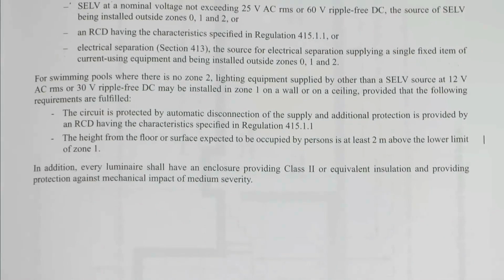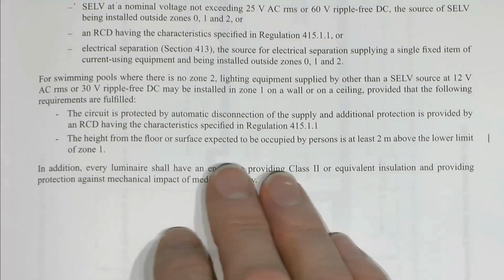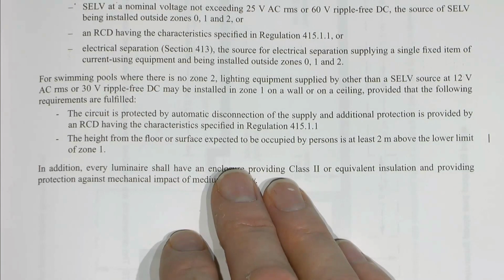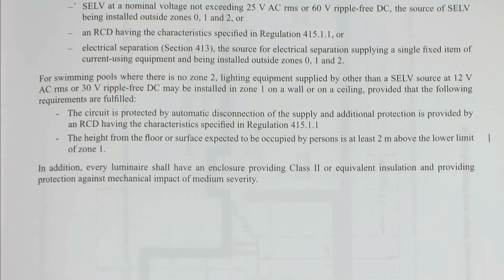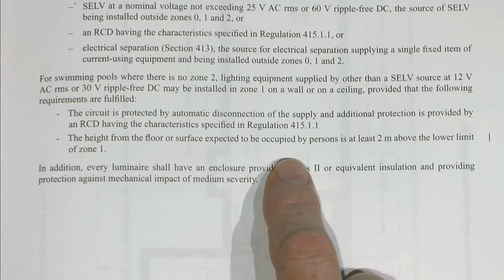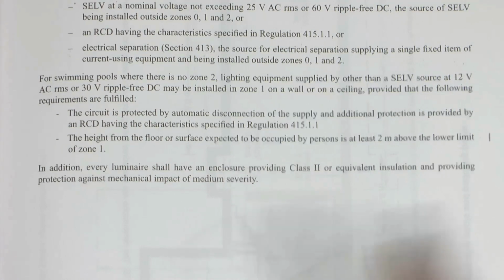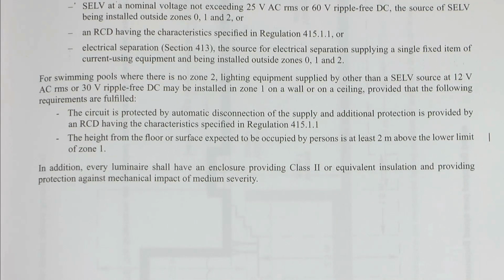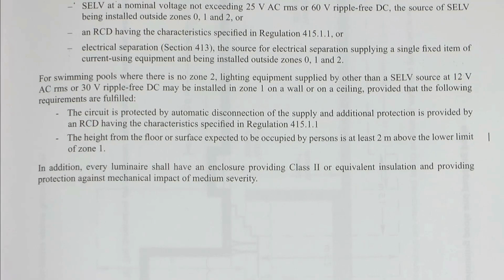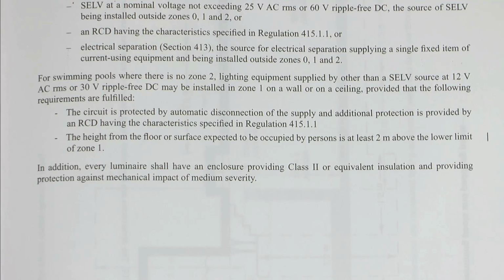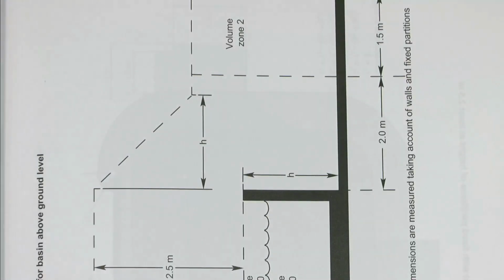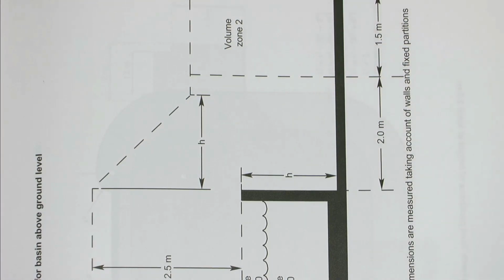The bit that's changed is this piece here, and the height from the floor or surface expected to be occupied by persons is at least 2 metres above the lower limit of Zone 1. Previously that didn't have the occupied by persons bit in it, so it's pretty much the same sentence. It was just previously 2 metres above the lower limit of Zone 1. Now it only applies for those that are going to be occupied by persons. So a fairly minor change there, nothing too different about that.